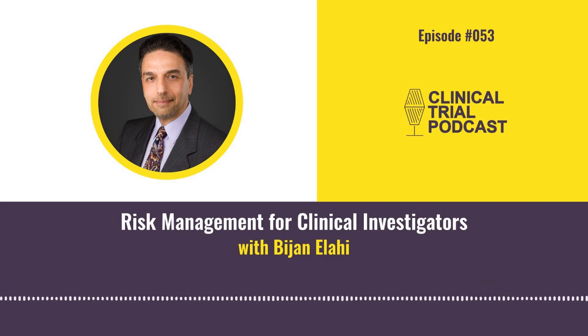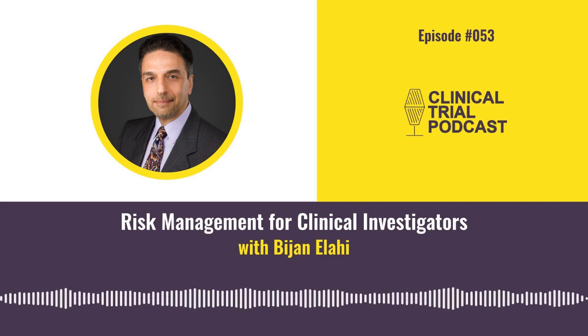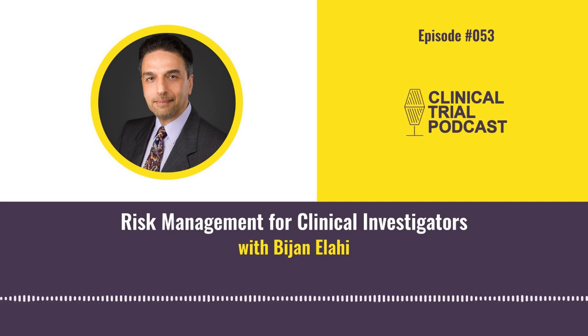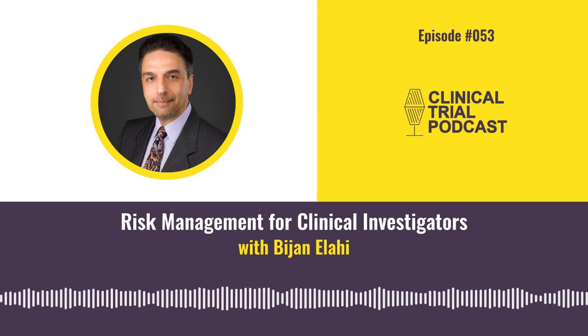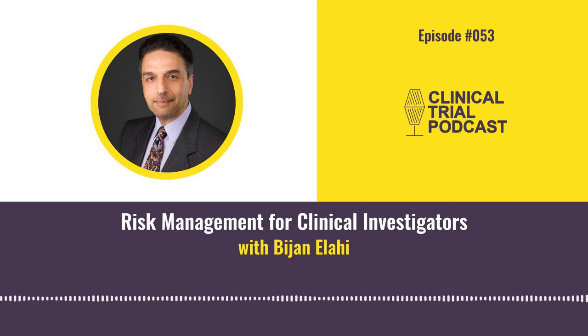the best and easiest way is to conform to a recognized or a harmonized standard. And these are key words. Recognized in America is when the FDA says we recognize the standard. In the United States, the FDA recognizes ISO 14971:2019, which is the third edition. And in Europe, there is a harmonized version of the standard called EN ISO 14971:2019 plus A11:2021. Kind of a mouthful, but that's a harmonized version of the 2019 version of the standard, which is recognized by the European Union. So in both cases, both Europe and the US, conformance to ISO 14971 will confer a presumption of conformity with the safety and performance requirements that both regulations expect.